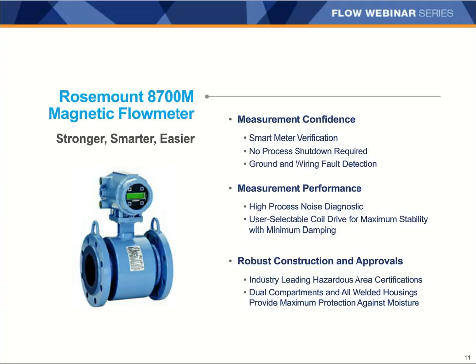Historically, another thing that has been tricky with mag meters is verifying their calibration. It typically involved removing the flow meter from the line or using extra equipment. Smart meter verification is a diagnostic that provides calibration verification without having to remove the meter from the line or using external equipment. Smart meter verification performs diagnostics that compare baseline values for coil signature, coil resistance, and electrode resistance to verify the meter's magnetic field strength is unchanged and undisturbed from the factory and the flow measurement is correct.